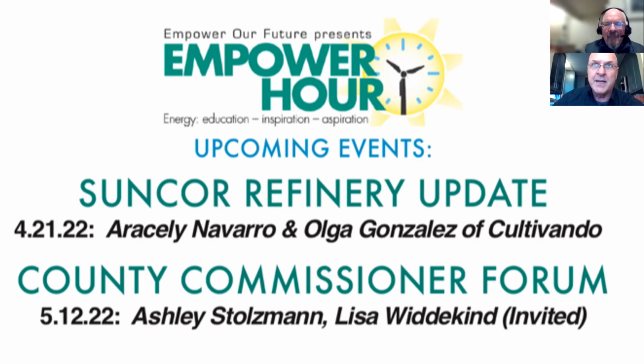Something has to come on first, and it has to establish the voltage and frequency in order for other things to start. If you just have solar on your roof and it's not a smart inverter, just a regular grid-tied inverter, it will not run when the power goes out, because it's looking for the grid frequency and voltage to operate. But if you and your neighbor could make a mini grid, your neighbor could fire up their smart inverter, which would create its own frequency and voltage, and then your grid-tied inverter would see that frequency and voltage and start as well. That's black start, something that starts everything to begin with.